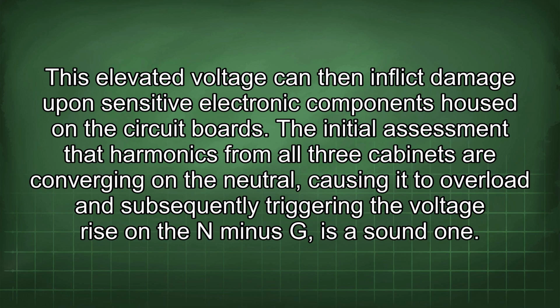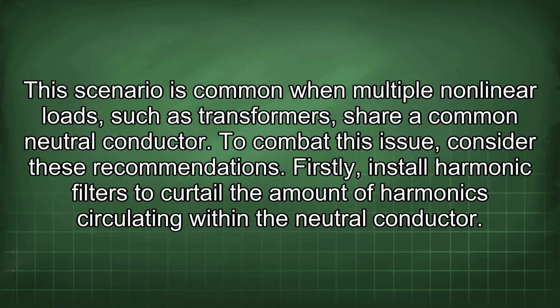The initial assessment that harmonics from all three cabinets are converging on the neutral, causing it to overload and subsequently triggering the voltage rise on the N-G, is a sound one. This scenario is common when multiple nonlinear loads, such as transformers, share a common neutral conductor. To combat this issue, consider these recommendations.